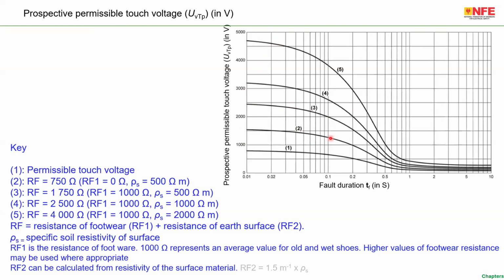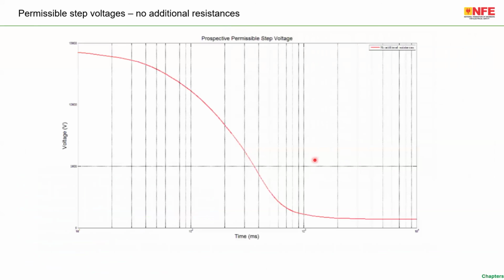practically, in a substation which we see on the roadside belonging to the distribution company, there are common people going to touch the extraneous parts or the fence or whatever. And in most cases, our transformers are also in exposed areas. So there is a likely chance of people without shoes, without protective gear, touching and getting electrocuted in the vicinity. So in a typical situation, graph number 1, where I'm moving the cursor, is applicable. That means in 1 second, the touch voltage has to be limited to a maximum allowed touch voltage of 115 volt.